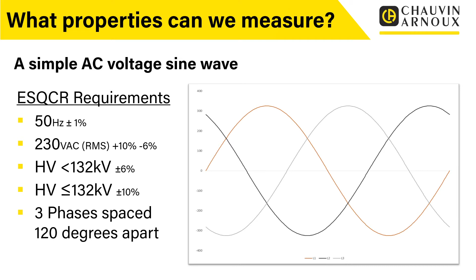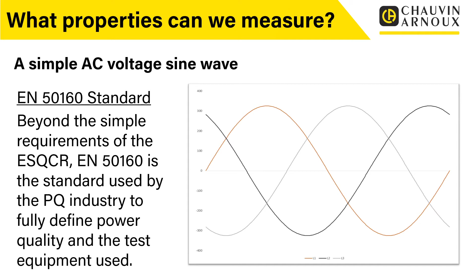Now, I mentioned earlier the EN standard 50160, and beyond the simple requirements of the ESQCR, which are very basic, we do have the requirements of EN 50160. This is the standard used by the power quality industry to fully define power quality and the test equipment used. So when you get more into the minutiae of it and actually understanding the individual terms and standards in there, if you get a copy of EN 50160 and have a look at the details, everything is defined to minute detail. That's really when you start getting more into power quality, you'll see the details of what you need to know are really in that standard, and that standard is really the basis for all power quality measurement.